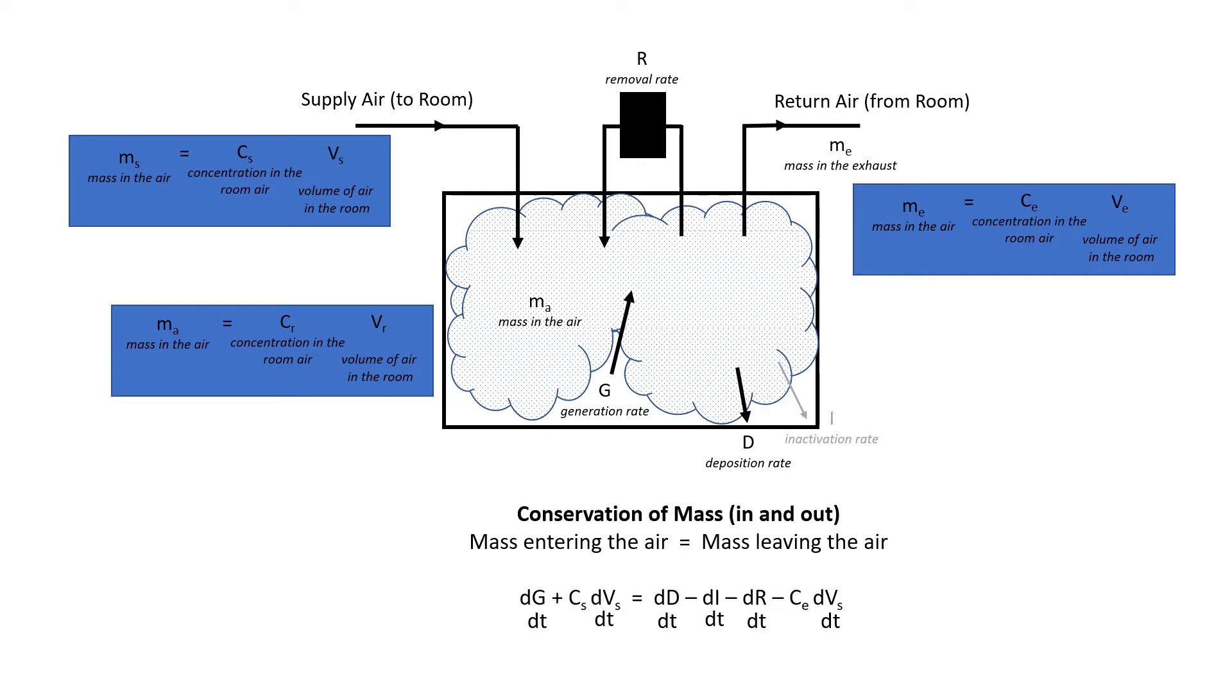What we're usually doing, though, is we're looking at mass flow rates into and out of the room in order to determine those concentrations. And so we're looking at generation rate as a function of time, the supply air, contaminants coming in the supply air as a function of time, deposition as a function of time, inactivation as a function of time, removal as a function of time, and exhaust air removal as a function of time. So those are all based on a function of time.